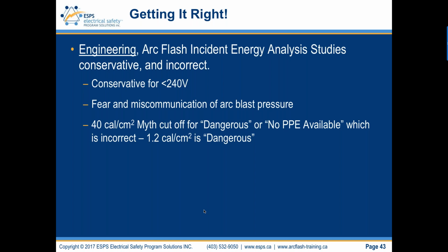It's actually taking us down a path that we don't want to go. The 40 cal myth: the cutoff for dangerous or no PPE available. Unfortunately, the power engineering software propagated this problem. It caused it to grow. And now all the software has removed this correlation of the HRC table to the incident energy results, but you're going to have historical reports.